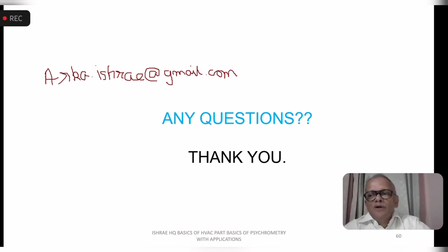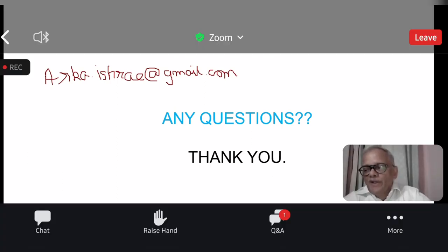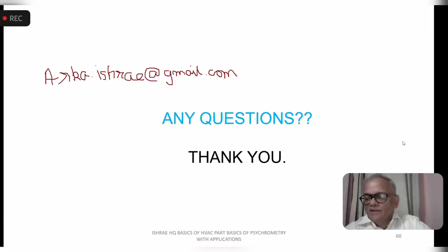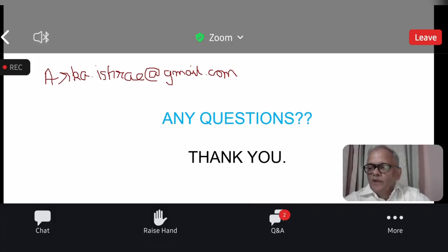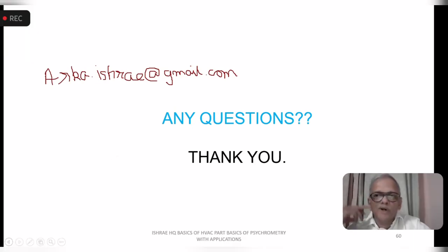So if you have moisture content not controlled, and that's why you will find so many books written on moisture control, and that is the biggest challenge the HVAC engineer has. There are antifungal paints available, but that is a remedy. Like you are having a headache, you take a Saridon. You are not removing the cause, you are only removing the effect. To prevent condensation or fungus growth, humidity control is important. So there are articles, there are books.